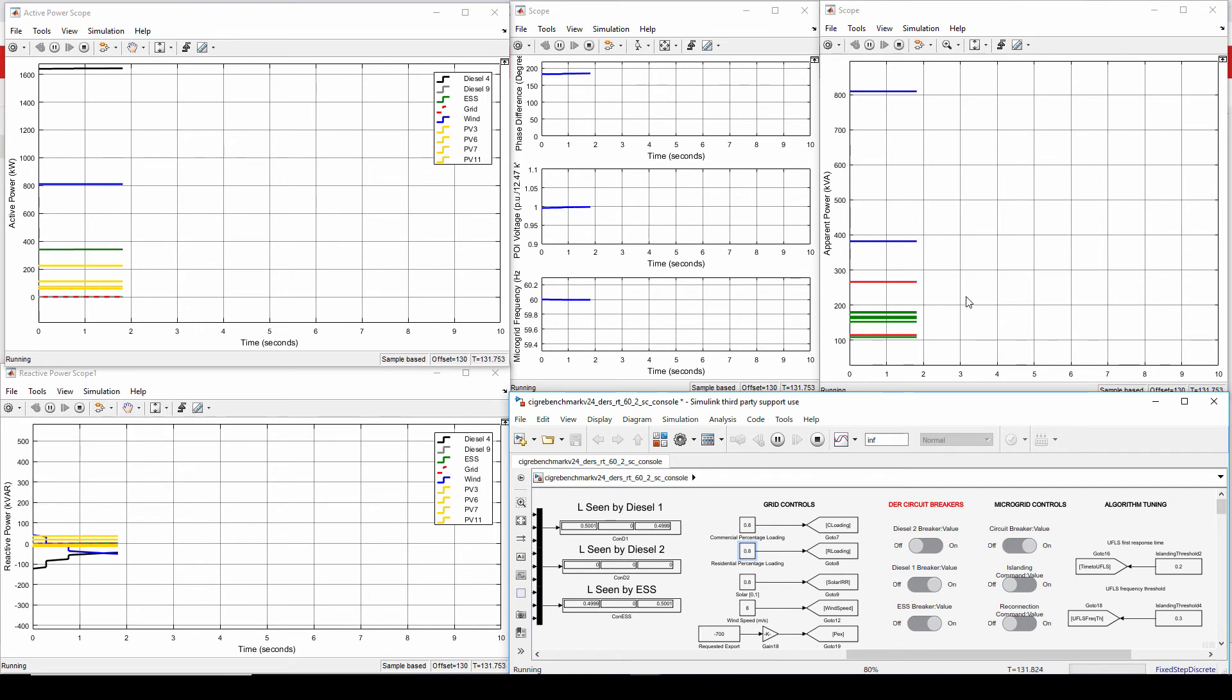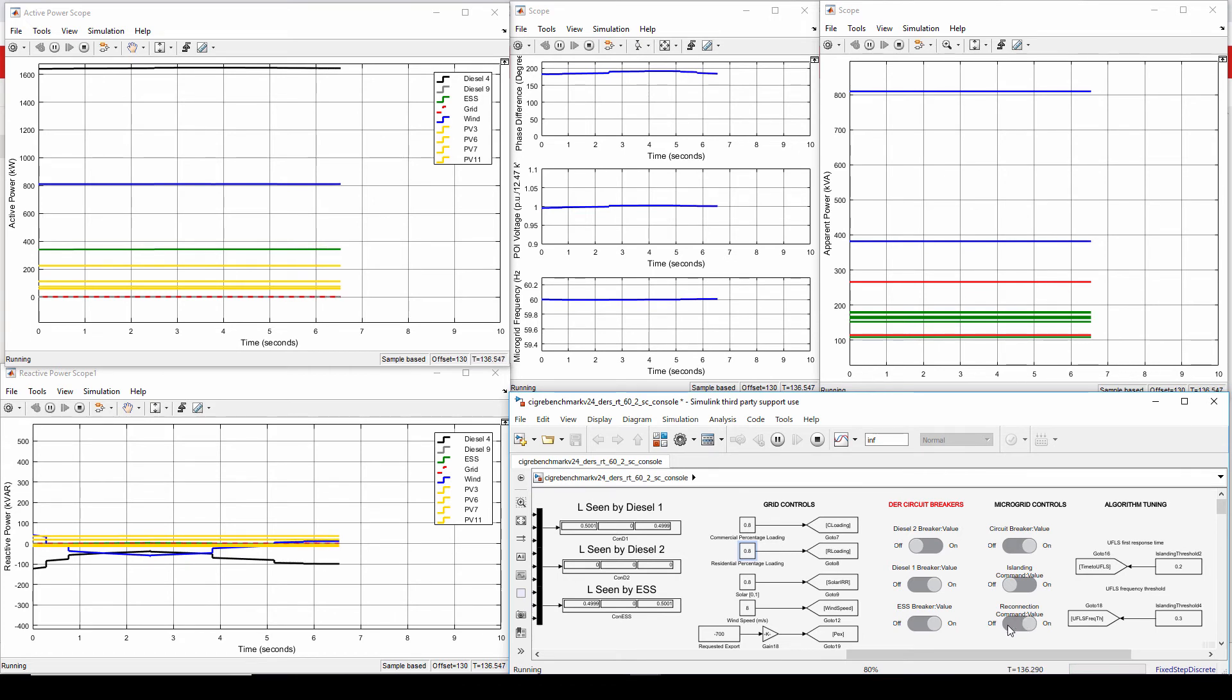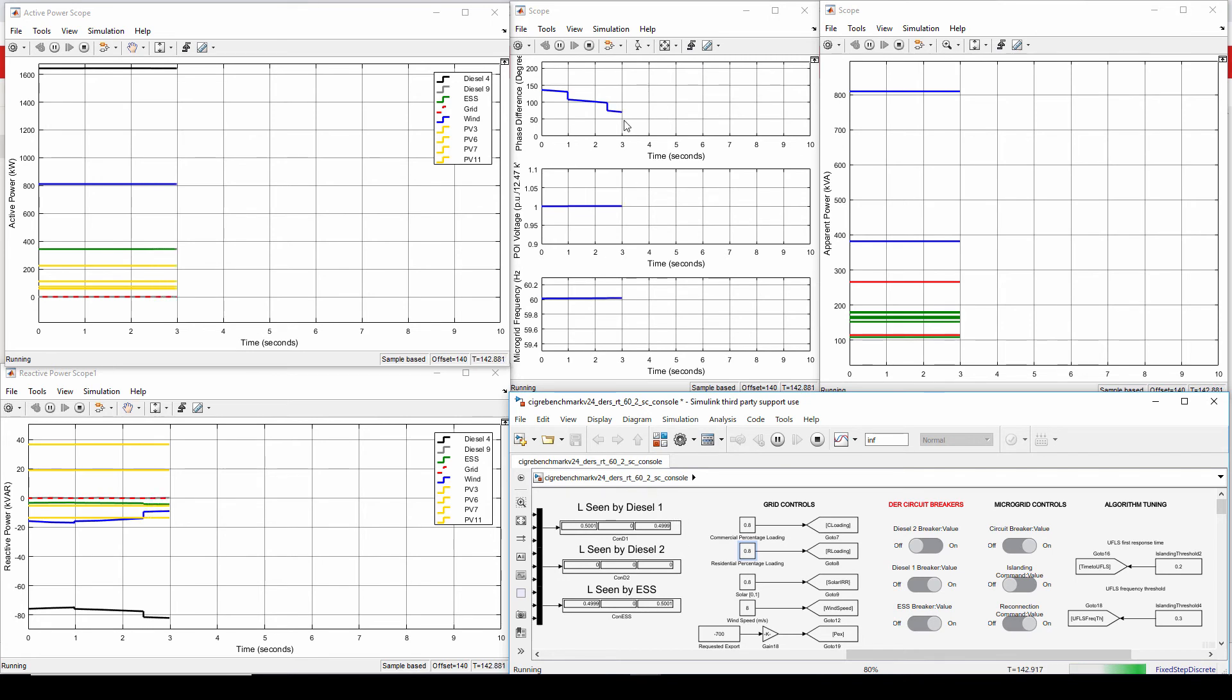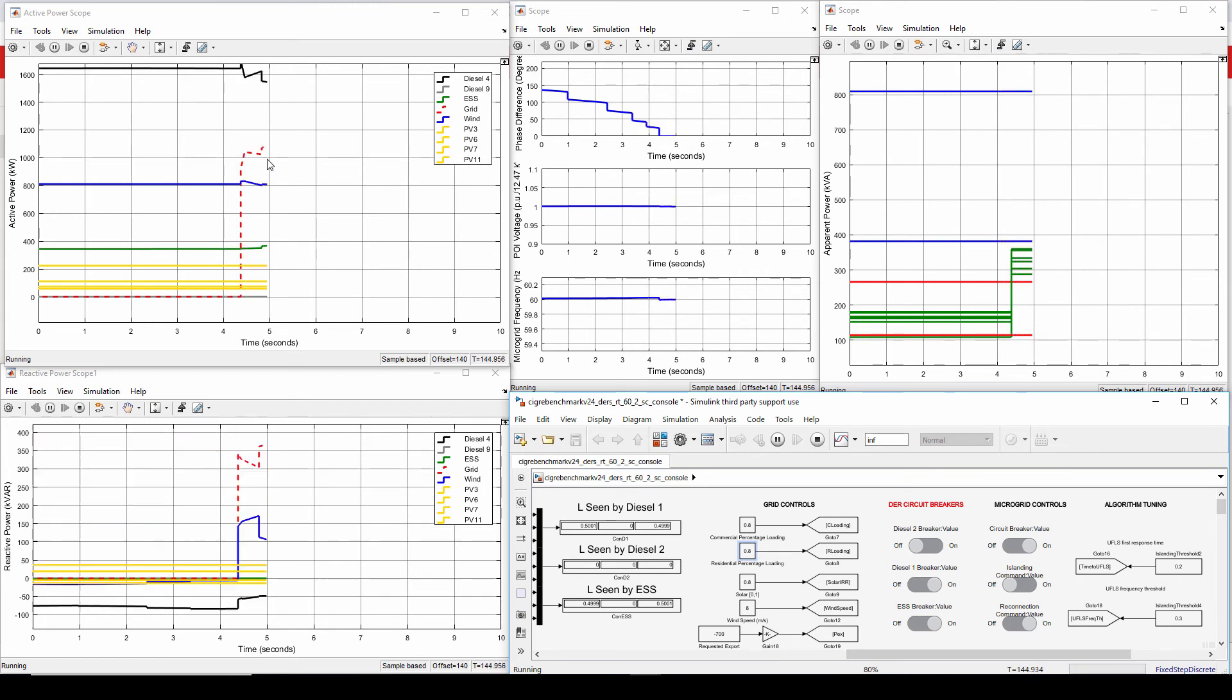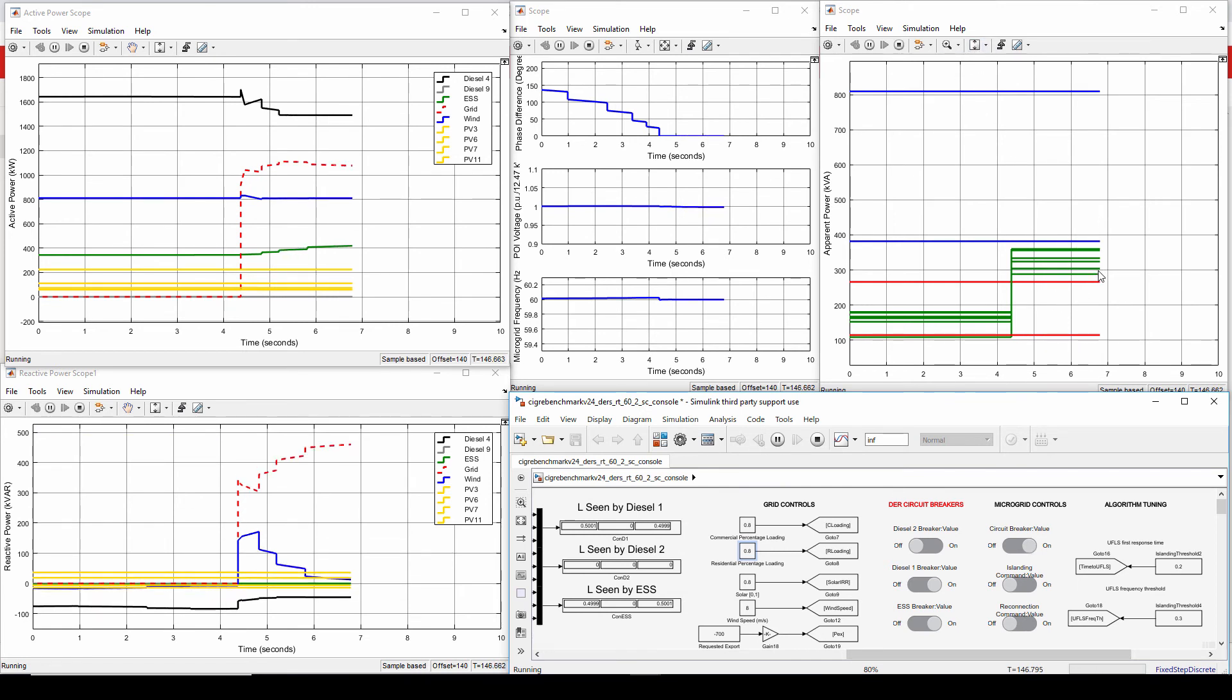Okay, so this is how much power I can provide in islanded mode. And now I'm going to issue reconnection so I can show you unplanned islanding scenario. And for reconnection purposes, as we all know, we need to synchronize the phase difference, the POI voltage and the microgrid frequency. The microgrid frequency and the POI voltage are already being regulated at their nominal value. So what's happening now is that the phase difference is being cancelled by the ESS and the diesel generator which are running. And as we can see here, it is now converging to zero and at any time now it's going to, okay, it's just reconnected. And the loads are also reconnected back again to their nominal values.